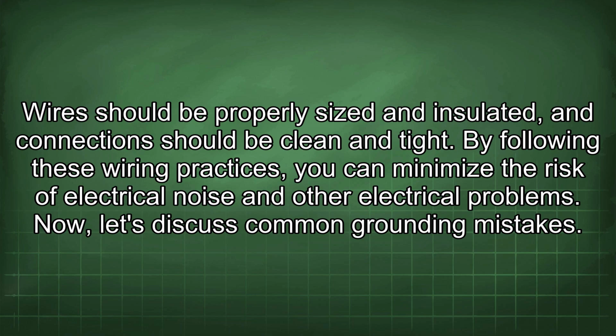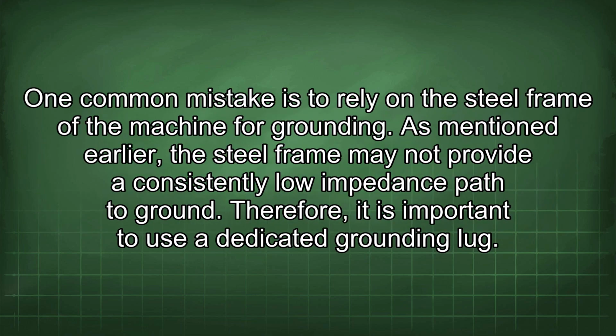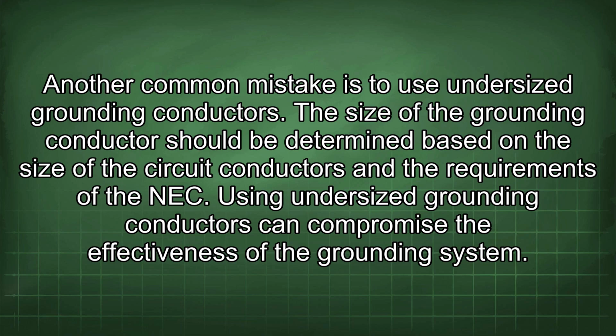Now let's discuss common grounding mistakes. One common mistake is to rely on the steel frame of a machine for grounding. As mentioned earlier, the steel frame may not provide a consistently low impedance path to ground. Therefore, it is important to use a dedicated grounding lug. Another common mistake is to use undersized grounding conductors. The size of the grounding conductor should be determined based on the size of the circuit conductors and the requirements of the NEC. Using undersized grounding conductors can compromise the effectiveness of the grounding system.